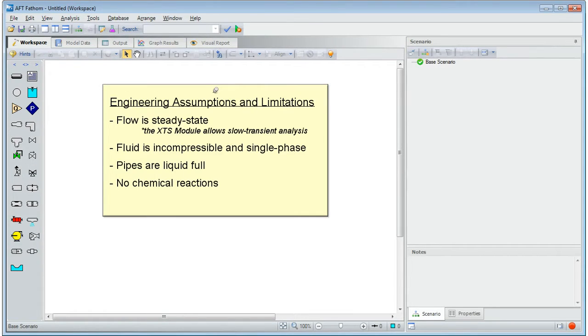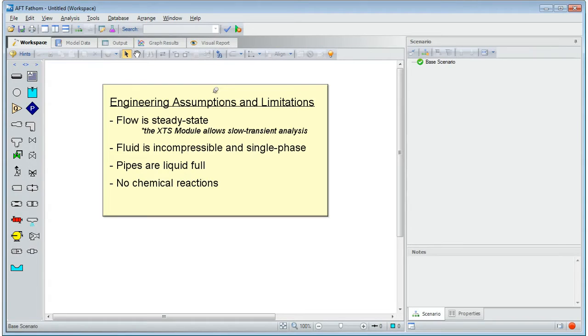The engineering assumptions and limitations required to use Fathom include flow being steady state, all fluids are incompressible and single-phase, all pipes must be liquid-full, and Fathom can't model the effects of chemical reactions throughout the system.